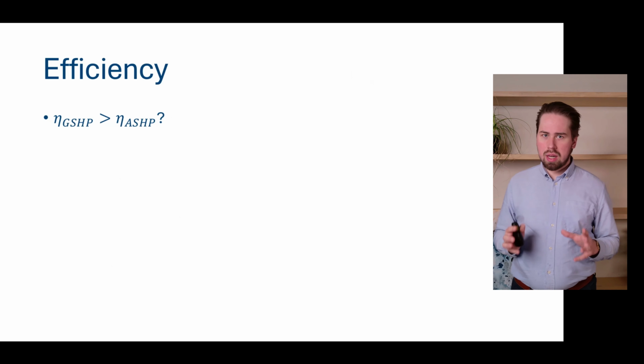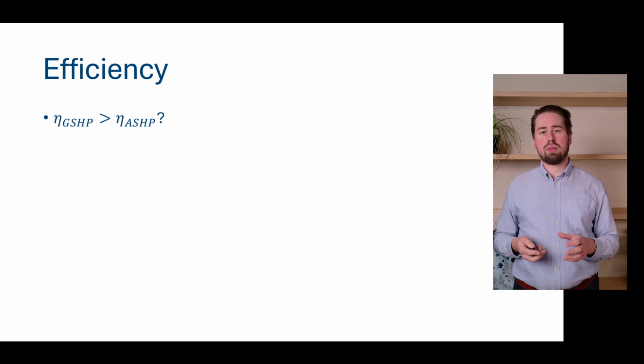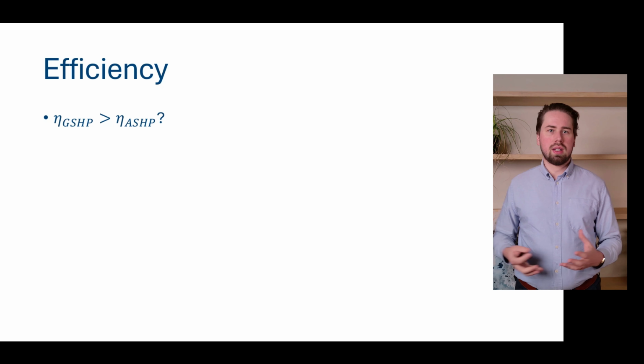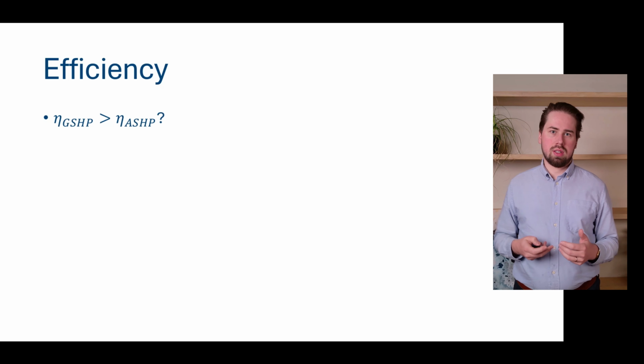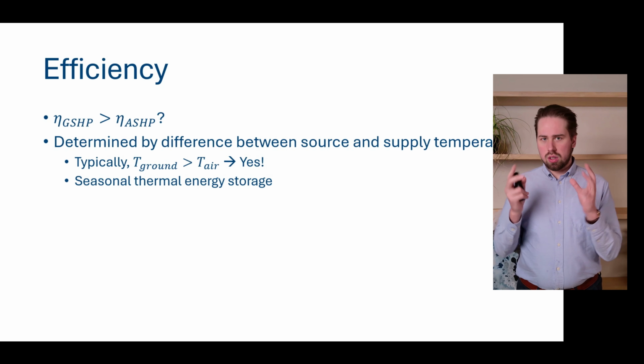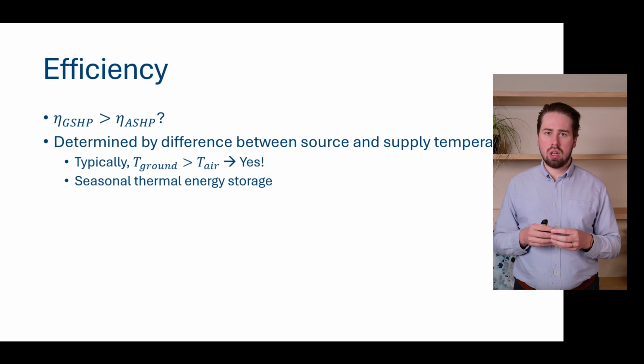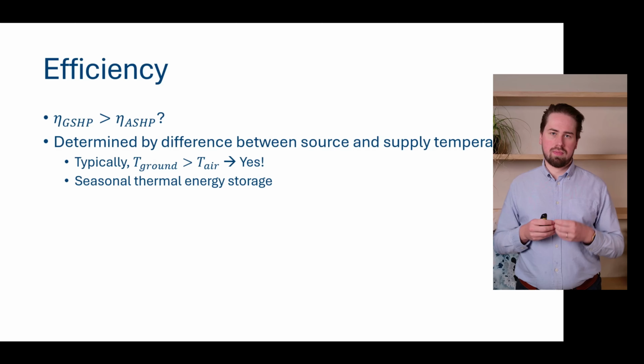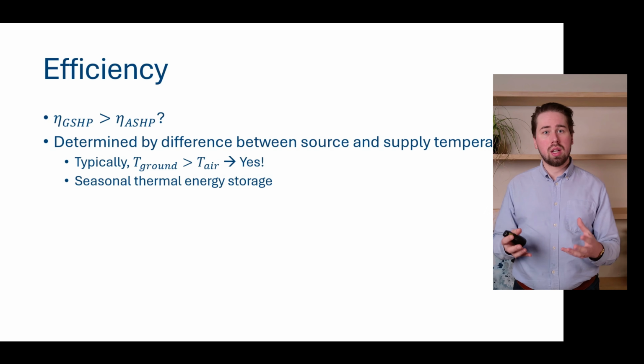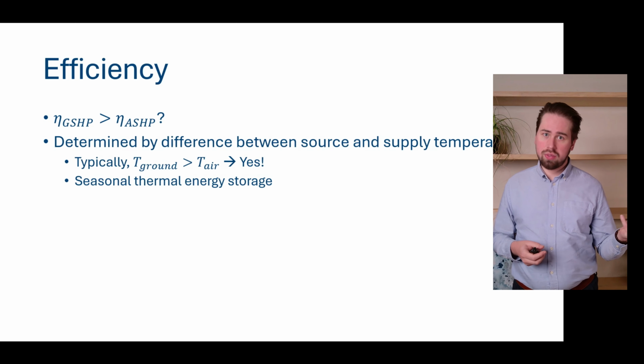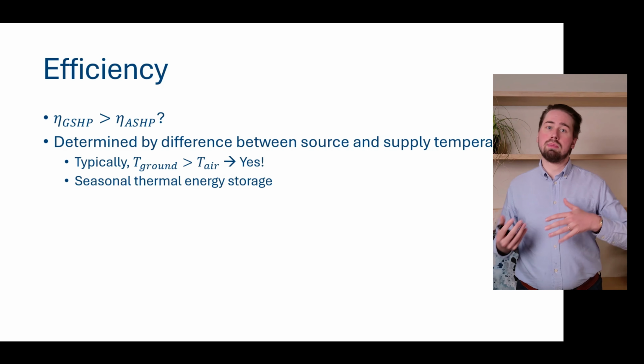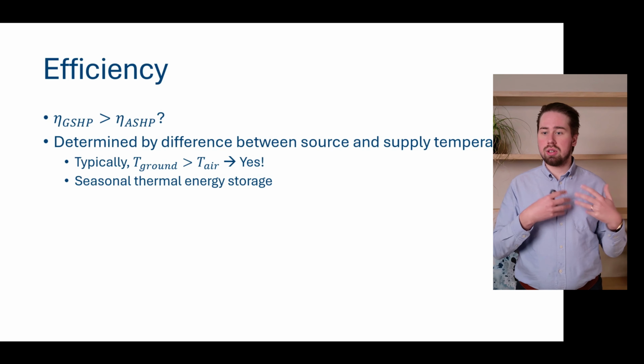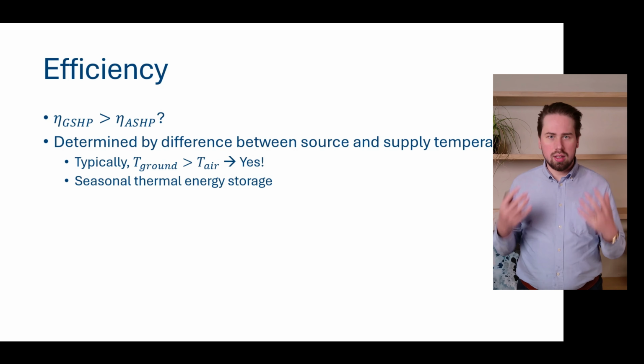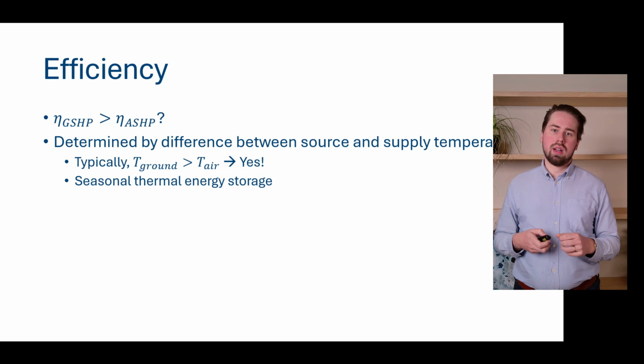Now, when we talk about the efficiency of ground source heat pumps, we typically know that they are better than air source heat pumps. The concept of efficiency, as we will discuss later in this part of the course, is that it depends on the source and the supply temperature. Typically, our ground temperature is warmer than our air temperature in winter, whereby our ground source heat pump has a better efficiency than our air source heat pump. So yes, it typically has a better efficiency.